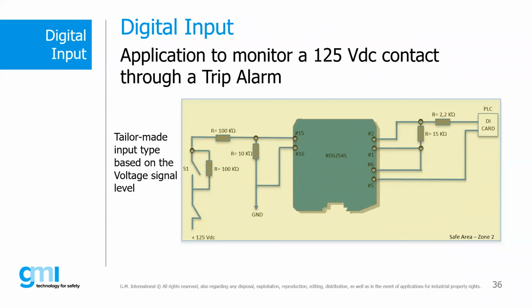The third state, fault in the field, for example a cable break at the input, will give us a fault at the output with the opening of the relay commanded by trip alarms. In this case, the PLC will see a fault status. Clearly, the PLC card must be of the supervised type. The output resistance on the device can be changed if the application requires it.